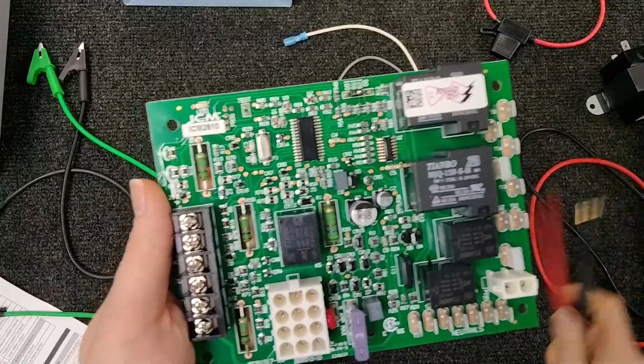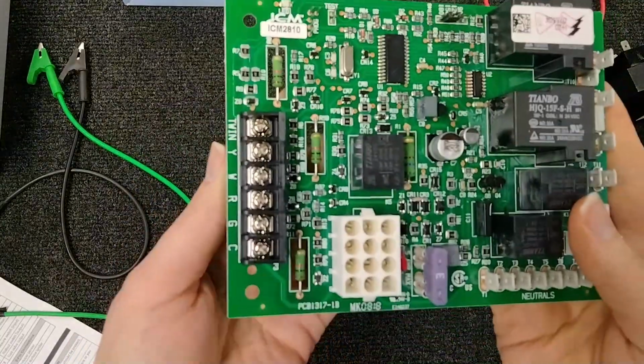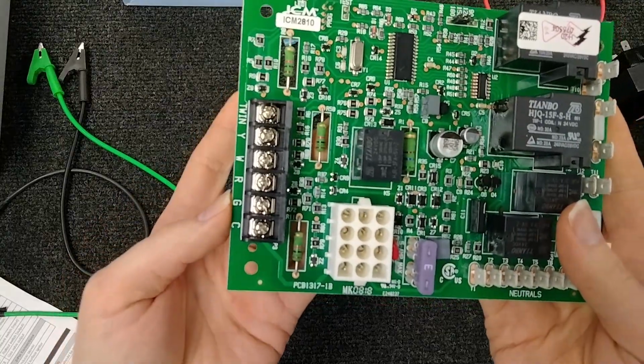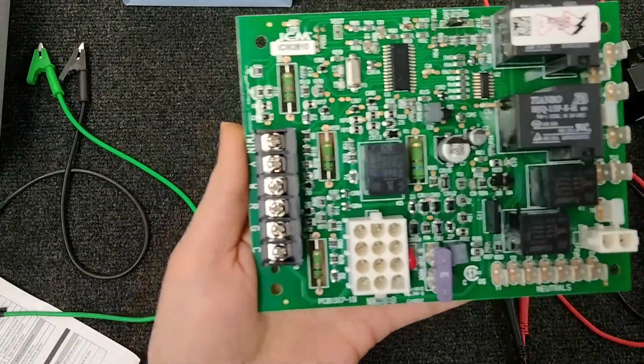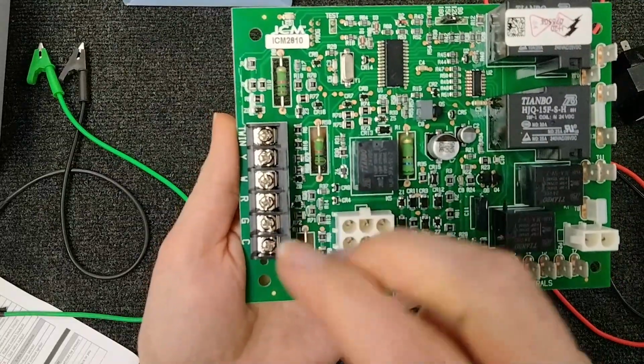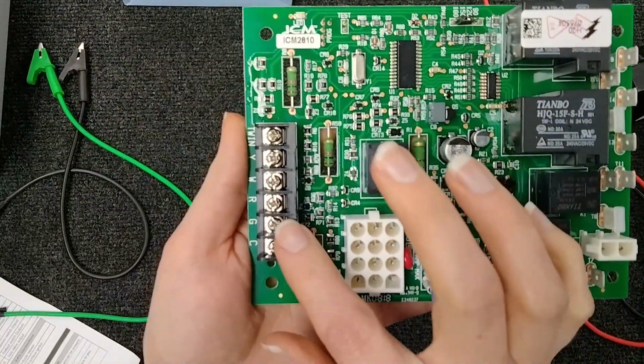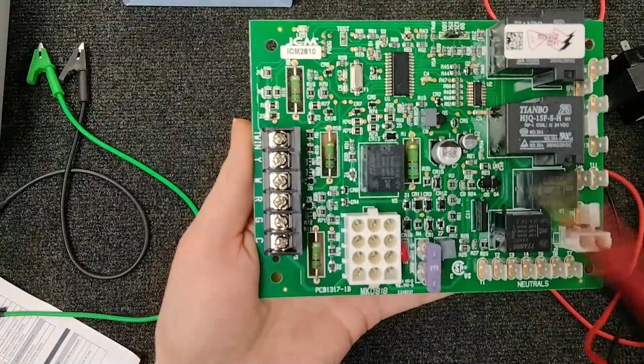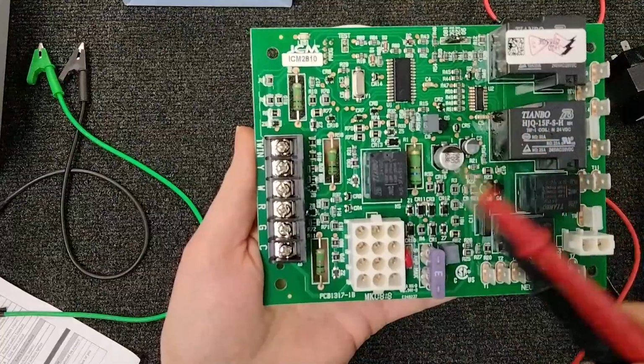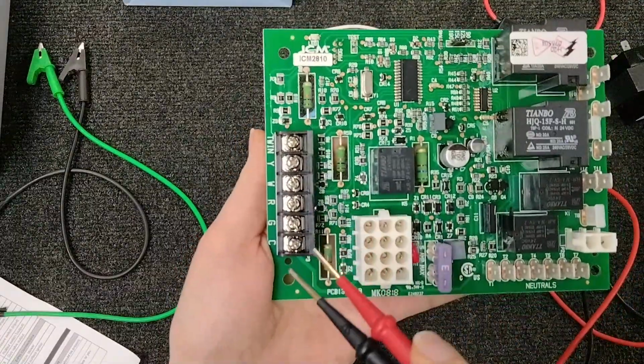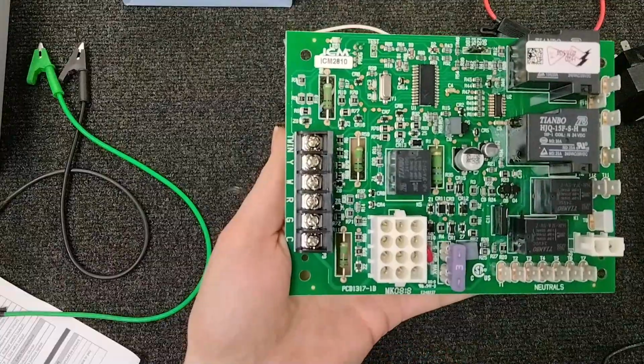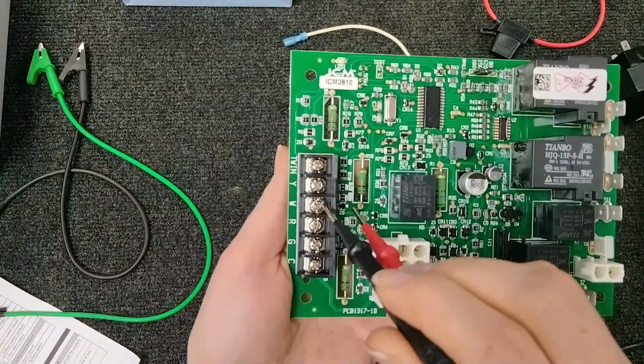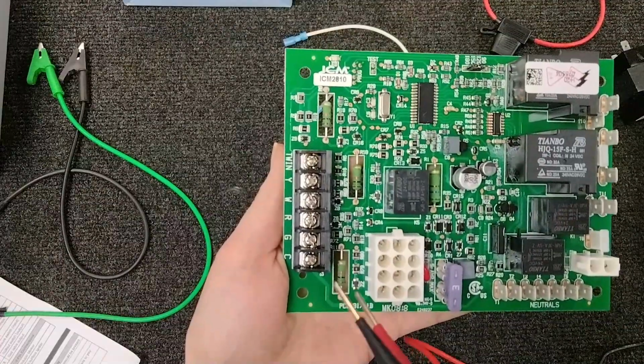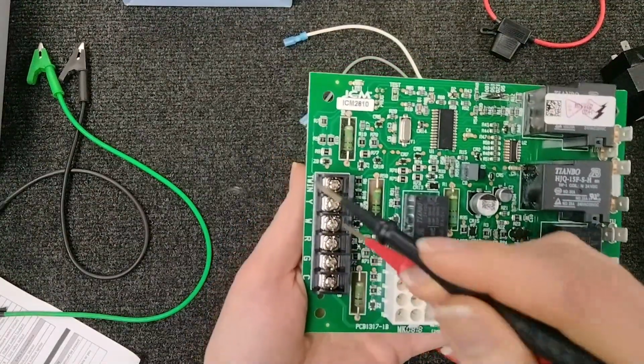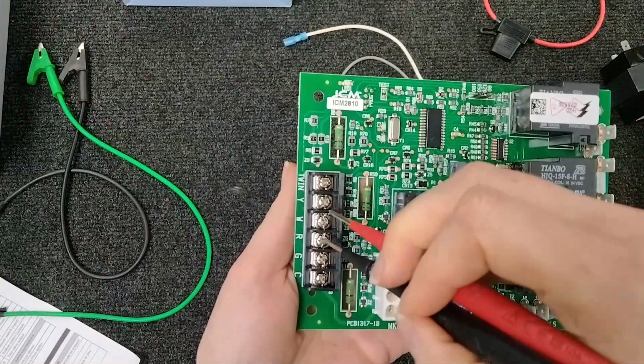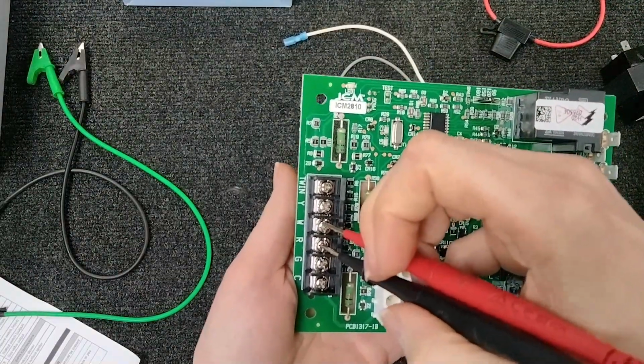2-stage can be a little different, but what we've got here is your basic setup for your thermostat wires. Now, when you're wanting to see if there is actually a call for heat on your control board, we need to find out if you're getting the 24 volts or the call from the thermostat here where your wires go. You're going to check between R and W, and this is your call for heat. R being your hot, W to get your heat to come on.